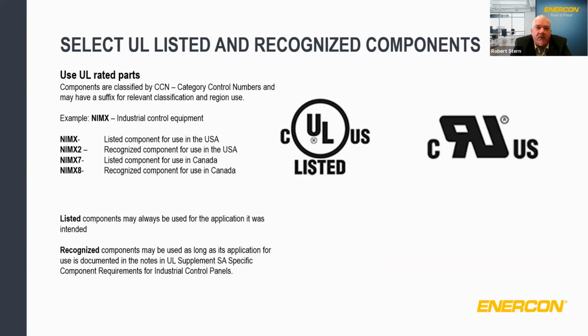Selecting UL listed or recognized components is very vital in compliance to the standard. UL uses a classification system called category control numbers, or CCNs, and they could have suffixes, and those suffixes are relevant to regional use or whether they're listed or recognized components. For example, NIMX, which covers industrial control equipment: if it's just NIMX with no suffix, that's a listed component for use in the USA. If it's NIMX2, that's a recognized component for use in the USA. NIMX7 is a listed component for use in Canada, and NIMX8 is a recognized component for use in Canada.